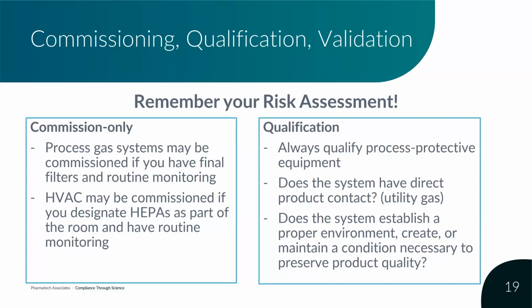If you designate your HEPA filters as part of your room, then the quality of the air within that room is defined only by that room system. So you may be able to commission only your HVAC. If you do that, with routine monitoring, and say my HEPA filters are part of the room, it's possible to only commission your HVAC. This is a thing you will have to have done risk assessment on so that you can justify the decision when someone asks you about it later — and they will.